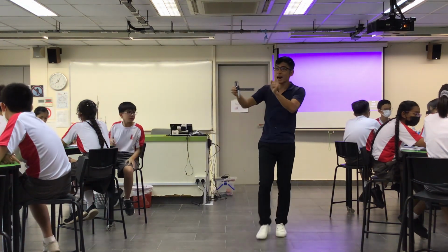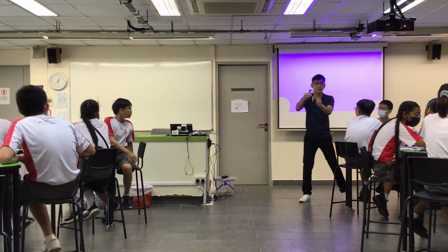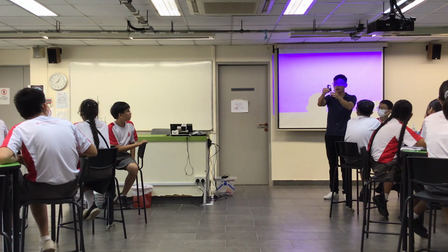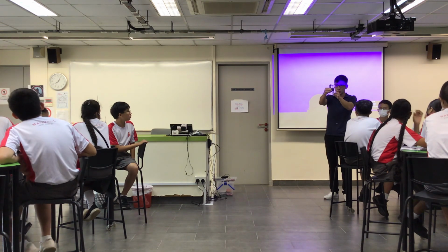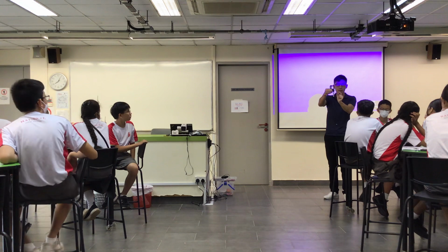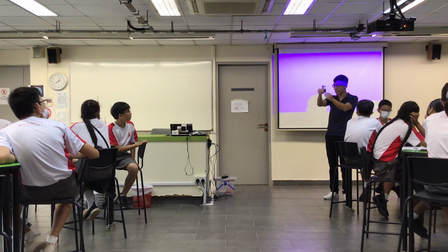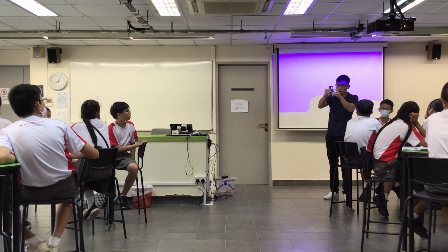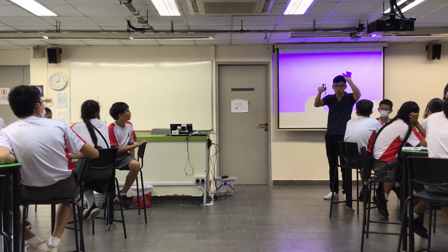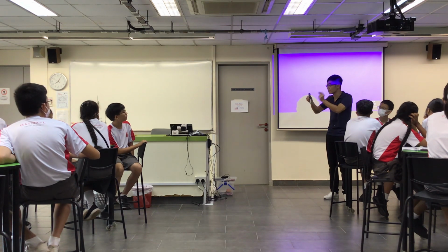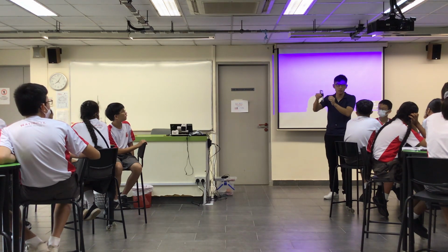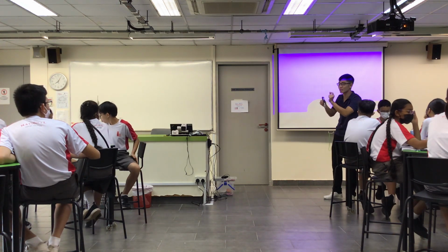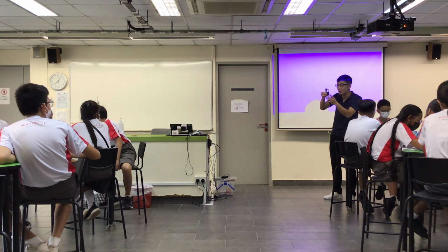The time when students break this instrument is when they close it. You know why? When they close it, sometimes they close too hard. There's a limit. If after you close and it hits the top, you try to screw any more, you damage this whole thing. On the top and bottom of these 2 clamps, there's a very sensitive sensor. If you clamp it too hard, you'll damage the sensors. So whatever you do, the bottom line is, just be extremely gentle. The moment you hit the limit, just stop already.